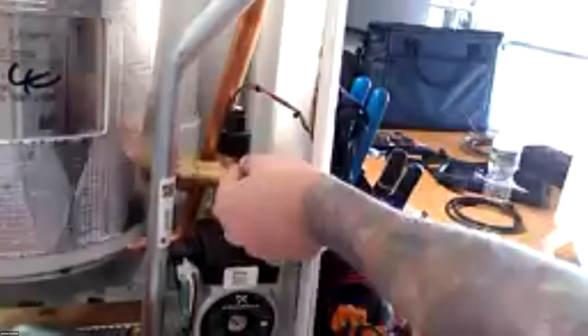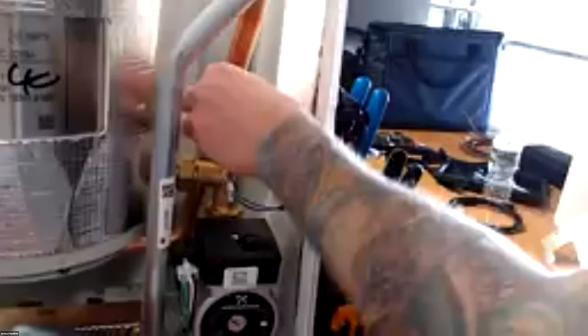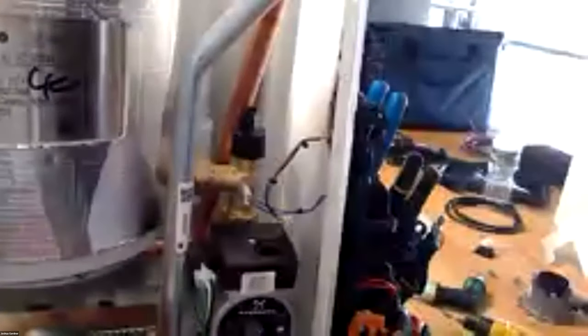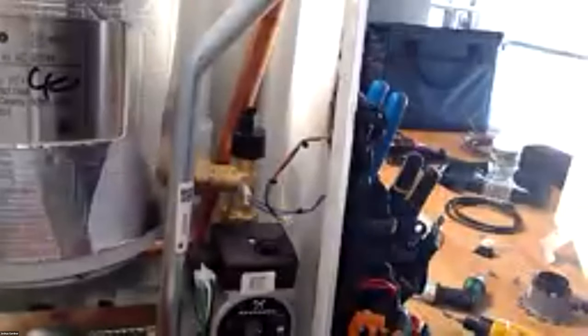What you're going to do is remove the pin right here, and your wiring connections. Just twist it and pull up. There's a little water cutoff. So if you're having pressure issues, you've got water on the system but you're not reading anything, pull this out and take a look inside, see if you have any debris in there that's preventing this thing from reading pressure. And for service, I think that's about it.